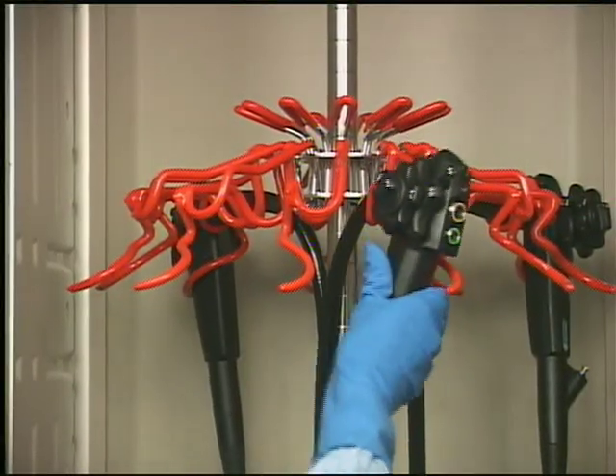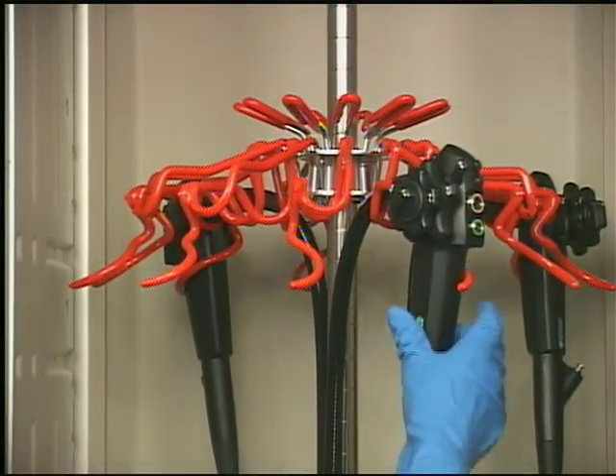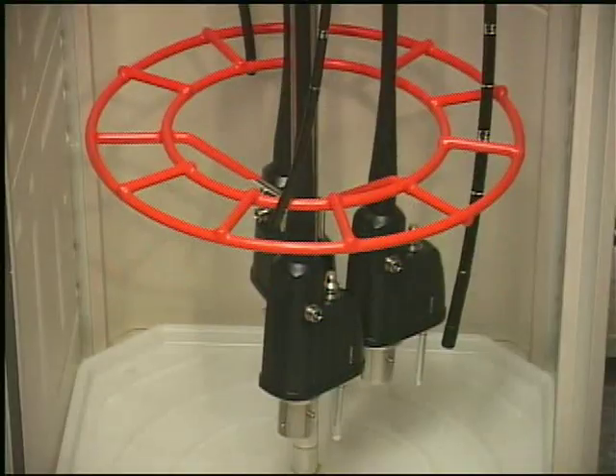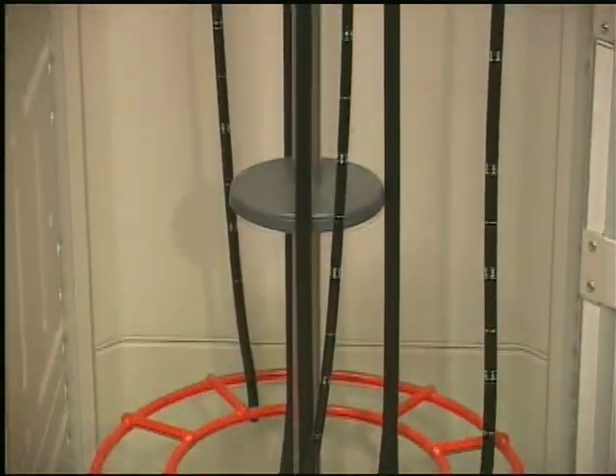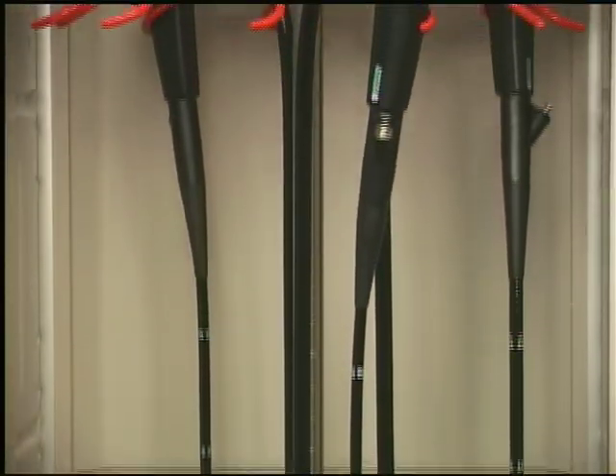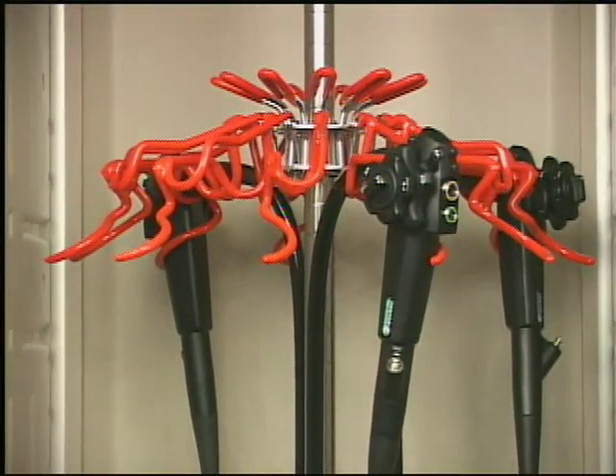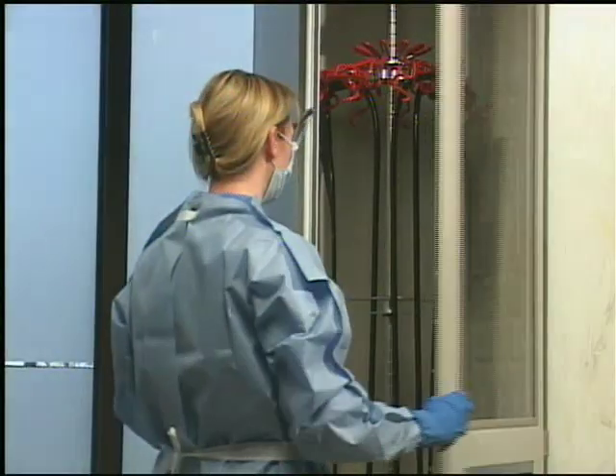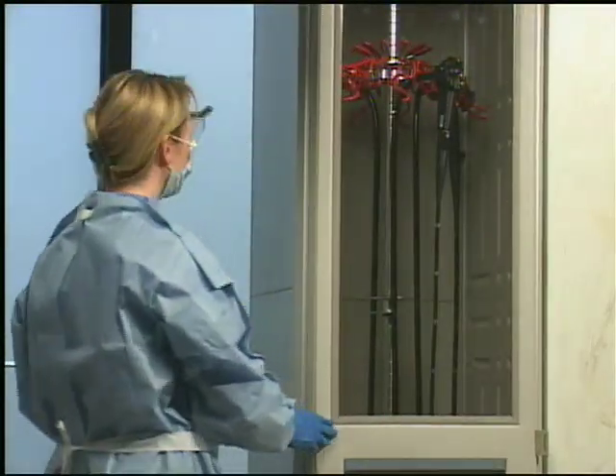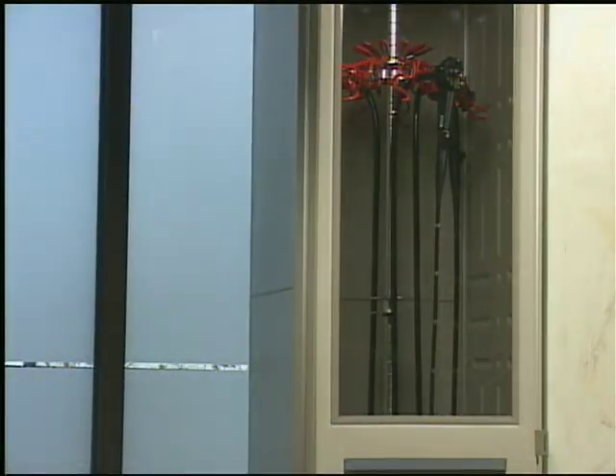The storage area should be dry and airy. Never store the endoscope in areas of high humidity, high temperatures, or in direct exposure to sunlight or X-rays. Never store the endoscope in its carrying case. Avoid storing in cabinets that have sharp edges or exposed nails or screws.